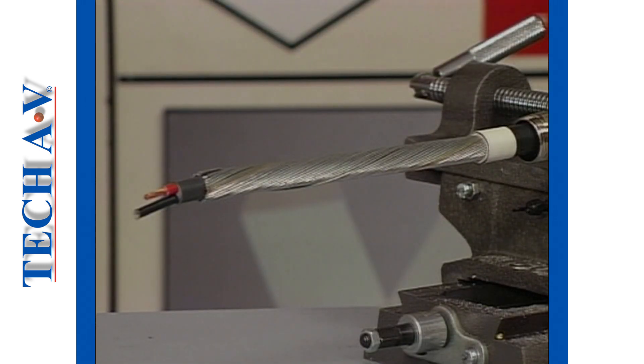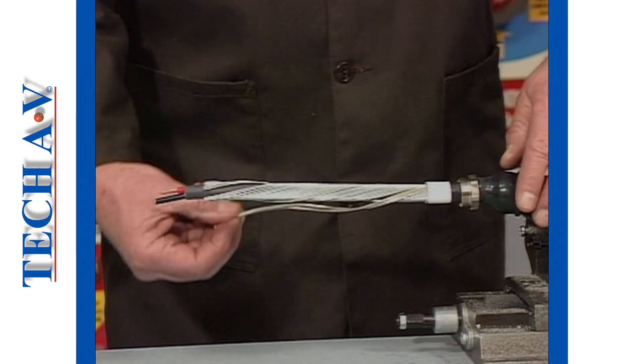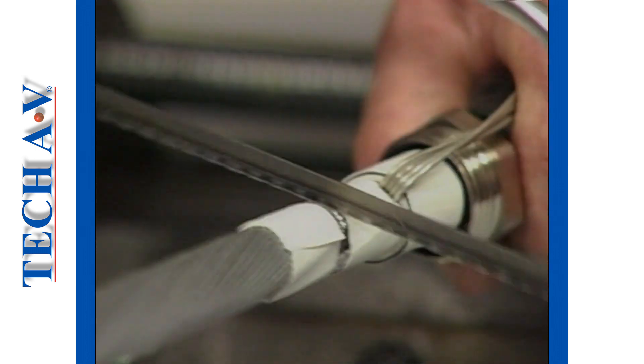Cable preparation begins by removing the outer sheath to the pre-measured length and then separating the steel armour strands as demonstrated. The steel armors can then be removed in the conventional manner by ring cutting and bending.